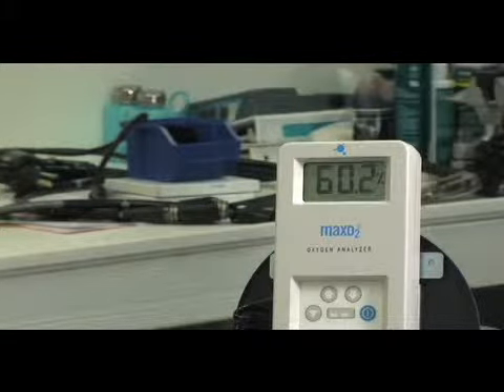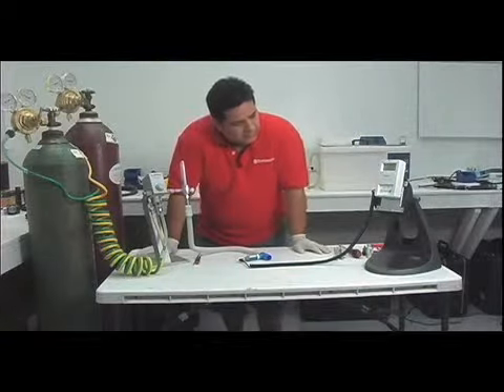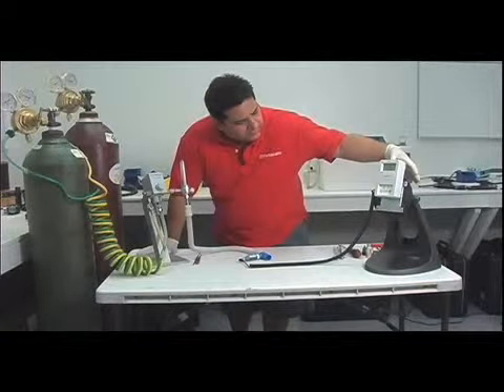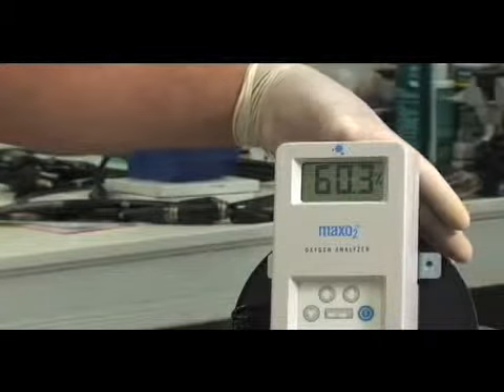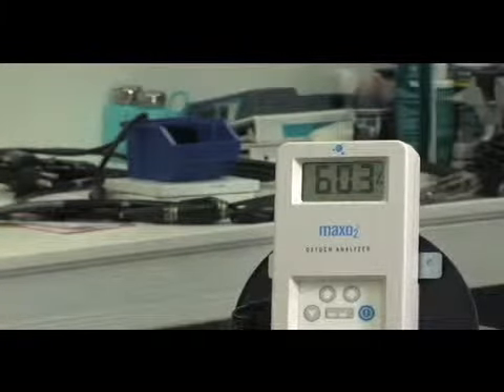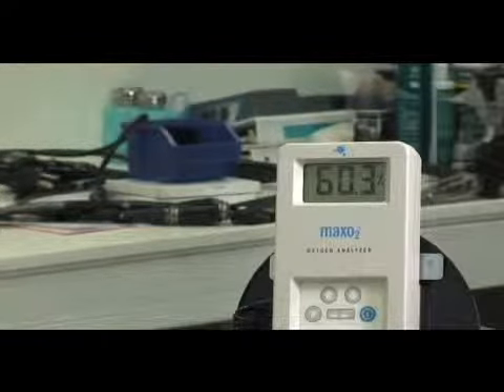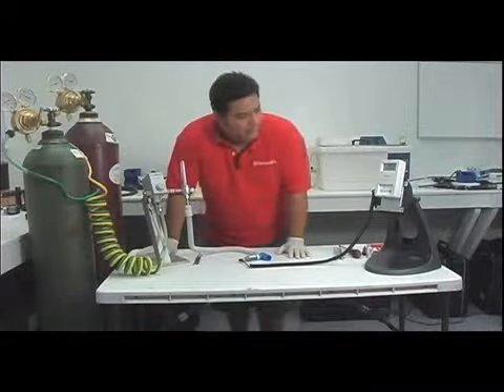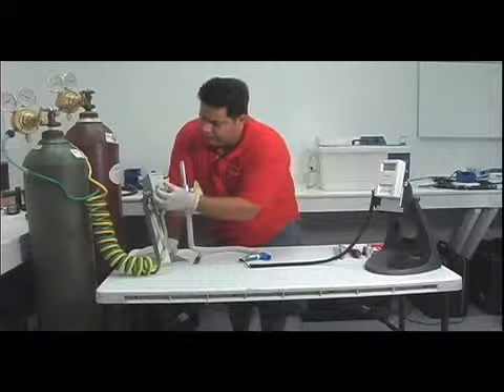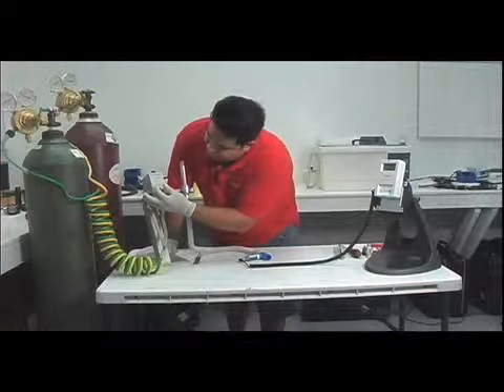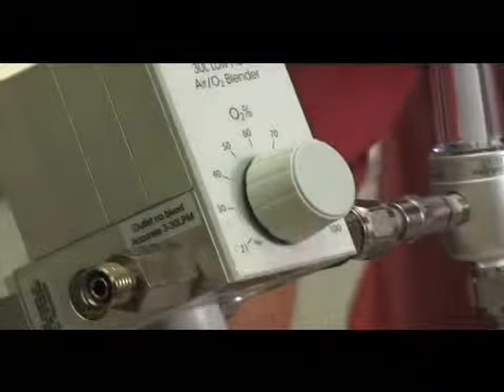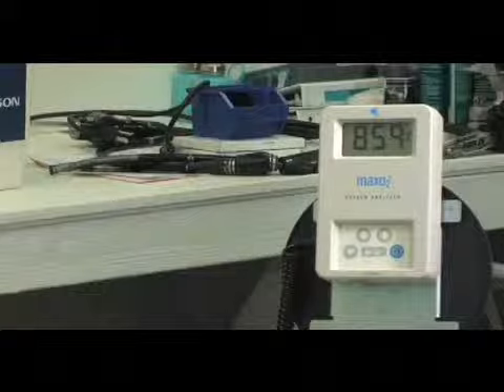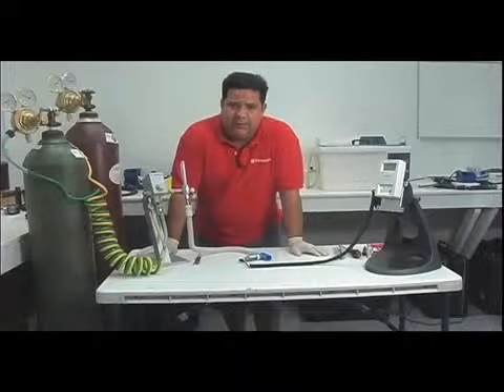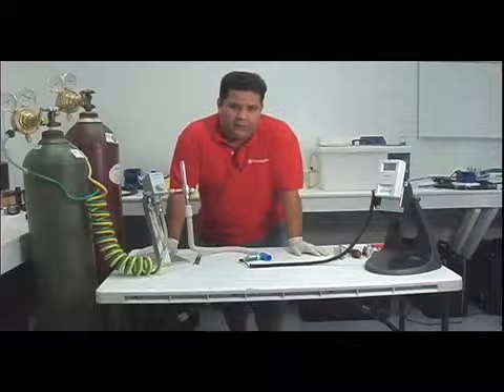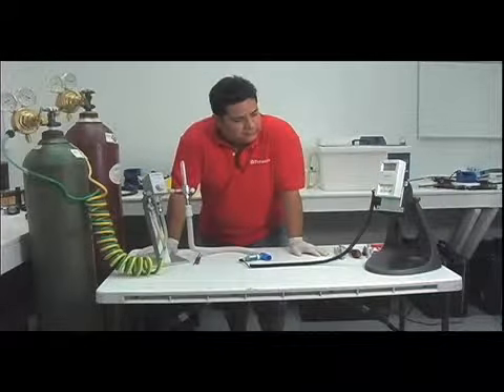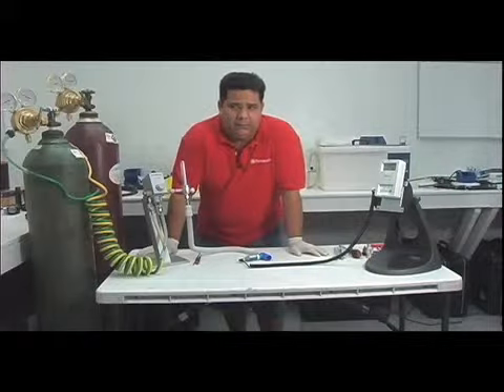We're at 60.2 so far. When you notice the oxygen analyzer going back and forth on a longer pace on something, it means it's finishing up to settle. So that's a good thing to show. We're gonna go and read our 90% and 100% just to wrap this up. So we dial to 90%, and at the end we're just gonna dial to 100%, and we can say that our calibration is done, finished, and we can proceed to the alarm calibration.